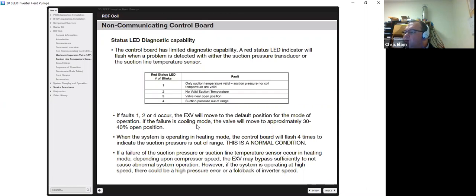If faults 1, 2, or 4 occur, the EXV will move to a default position for the mode of operation. If failure is in cooling mode, the valve will approximately move to 30 or 40% open. So you'll still get some operation. When the unit is operating in heating mode, the control board will flash 4 times to indicate the suction pressure temperature is out of range. And that's a normal condition.